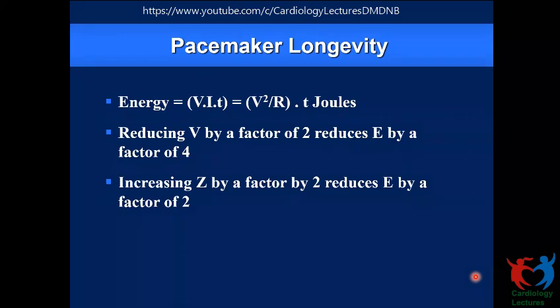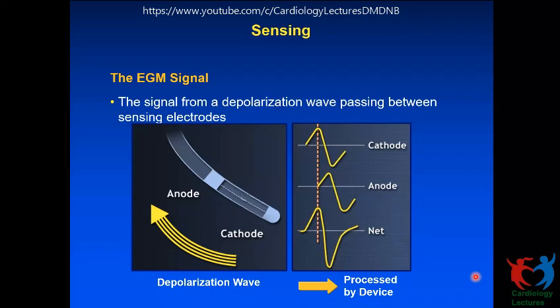Can I go ahead? Yeah, sure. Okay, right. So, the sensing part, quite a bit of it is described already, so I can shorten this. What the pacemaker measures is actually the intracardiac electrogram, the amplitude of the intracardiac electrogram between two electrodes, if it is the bipolar one. And if it is unipolar, if it's a true unipolar, electrogram amplitude is what is measured.